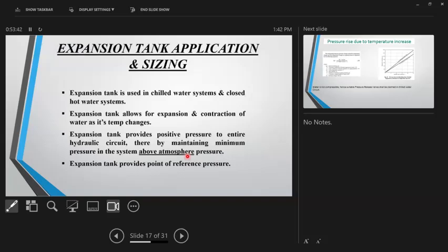Next important after the pump is the expansion tank. Now, an expansion tank is required in closed water systems, chilled water systems or hot water systems. We all know that. And what is the intent of the expansion tank? It allows for expansion and contraction of water, because water changes its specific volume with respect to temperature. So if you don't have any system which absorbs this volume expansion, you have a problem. An expansion tank also provides a positive pressure to the entire system, thereby maintaining minimum pressure in the system above atmospheric pressure. This is very, very critical. We will see later what it means.